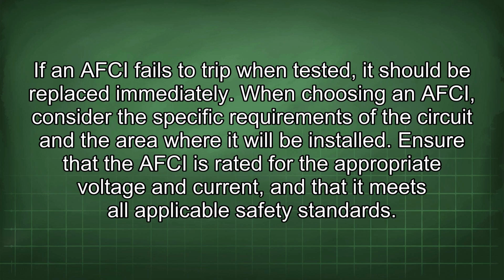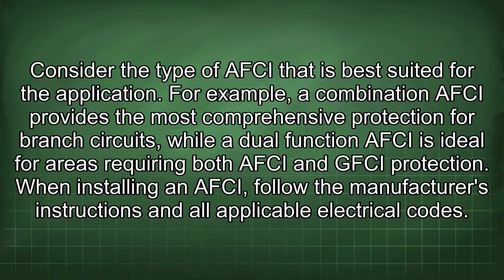When choosing an AFCI, consider the specific requirements of the circuit and the area where it will be installed. Ensure that the AFCI is rated for the appropriate voltage and current, and that it meets all applicable safety standards. Consider the type of AFCI that is best suited for the application. For example, a combination AFCI provides the most comprehensive protection for branch circuits, while a dual-function AFCI is ideal for areas requiring both AFCI and GFCI protection.